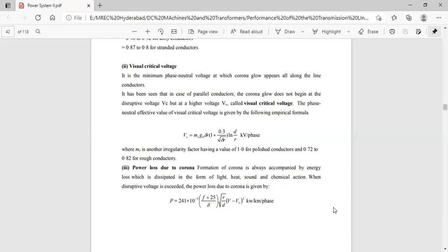The third, the power loss due to corona. Formation of corona is always accompanied by energy loss, which is dissipated in the form of light, heat, sound, and chemical actions. When the disruptive voltage is exceeded, the power loss due to corona is given by P = (241 × 10^-5) × (f + 25) / δ × √(r/d) × (V − Vc)² in kilowatts per kilometer per phase. So this is the power loss correlation for a system due to corona.